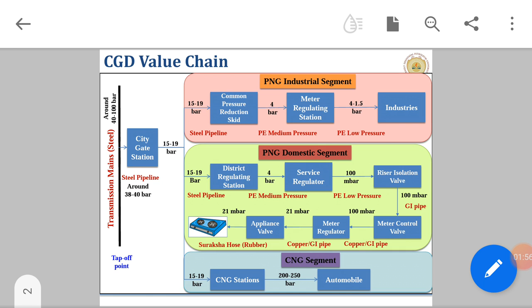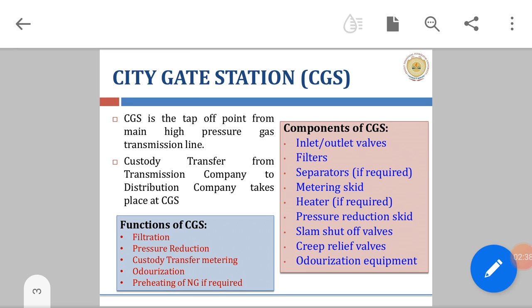Then the first component of the CGD value chain is the city gate station. CGS is the tap-off point from the main high pressure gas transmission line. Custody transfer from transmission company to distribution company takes place at CGS. The function of CGS is filtration, pressure reduction, custody transfer metering, odorization, preheating of NG if required. Components of CGS are inlet outlet valves, filters, separators if required, metering skid, heater, pressure reduction skid, slam shut-off valve, creep relief valve and odorization equipment.